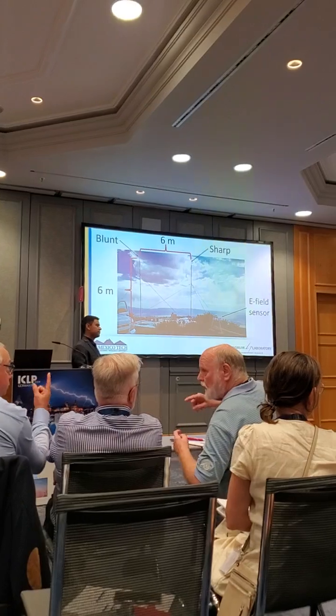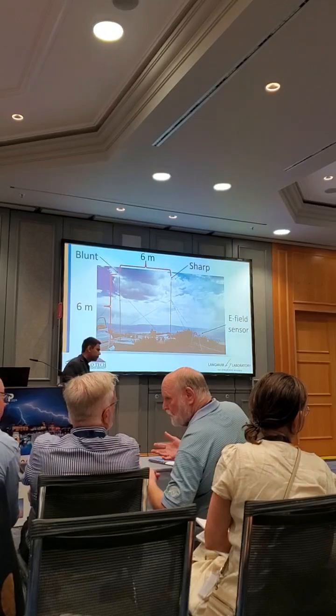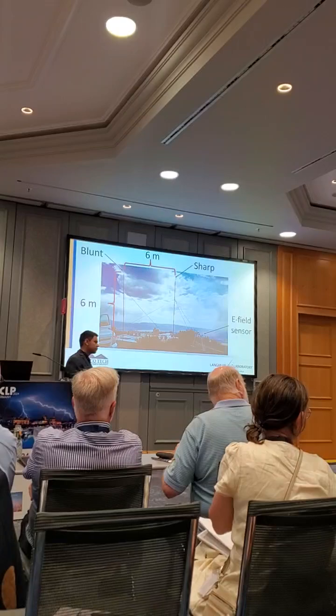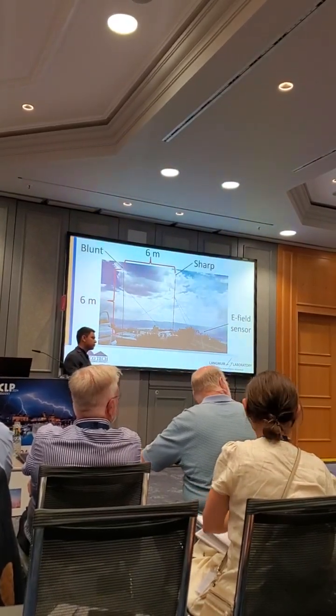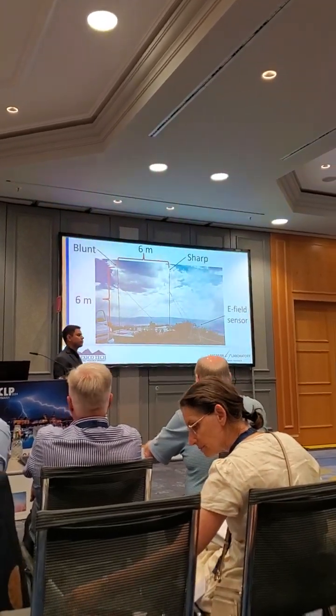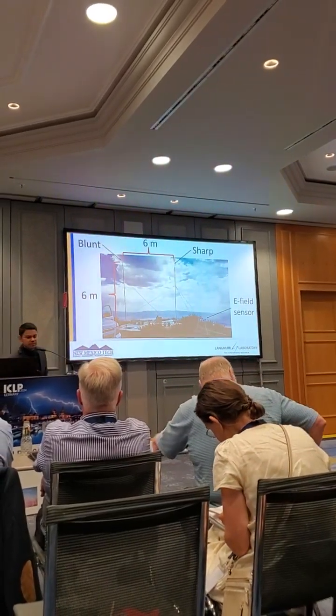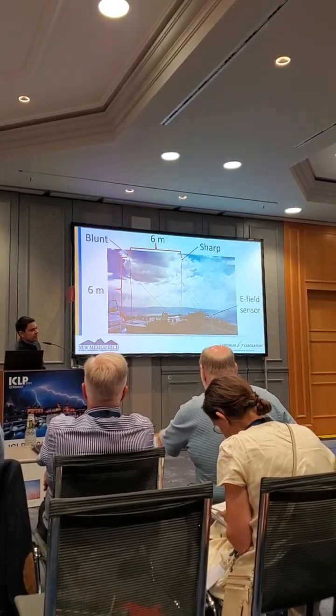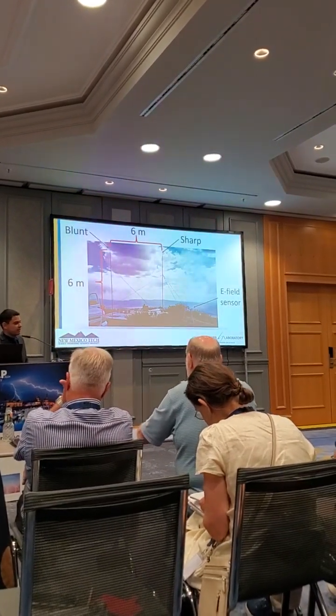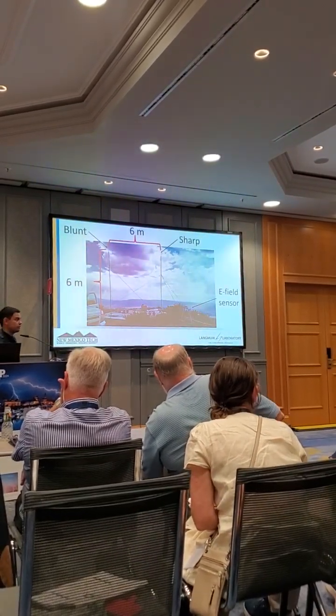Thanks. Interesting presentation. The question that I have is, I believe you stated in the presentation that the analog bandwidth of the current sensor that you're using is 500 kilohertz. I was wondering if you've done FFT analysis on those wave shapes that you have reported, to see what the bandwidth of the current that you're measuring is, and see if you might need a little higher bandwidth current sensor to be able to resolve those current wave shapes. Yeah, so that was the instrument that we had available this past summer. This summer we have upgraded to 10 megahertz. We haven't done any frequency analysis yet, but we can do it in the future. Thank you.